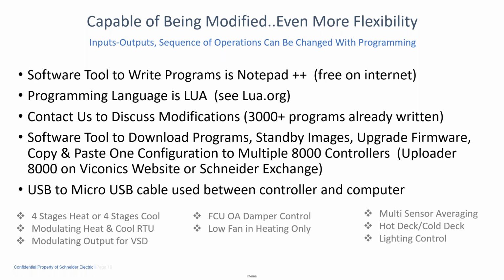If you've got a large installation, let's say a hotel or a dorm room where each one of the devices is configured exactly the same, you can save that configuration, plug into the next controller, and download that configuration so it's set up exactly the same way as the previous one. Again, this uploader tool is free on our website, or if you have access to the Schneider Exchange, you can get that tool as well. To put those programs into the controllers, you use a USB to micro USB cable. You probably already have one from some other electronic device. You plug it into your computer, you plug the other end into the controller, and you're able to do those modifications.